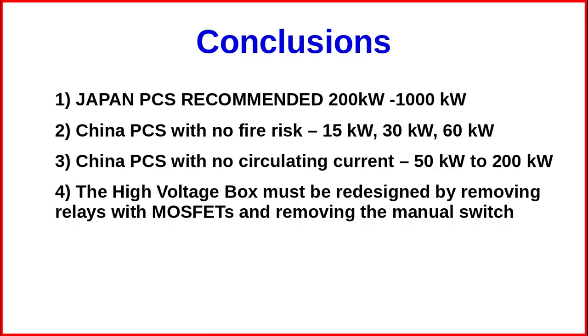Conclusions. One, Japan PCS is recommended for the range 200 kilowatt to 1000 kilowatt. Two, China PCS with no fire risk: these low voltage China PCS are recommended for BESS capacities of 15 kilowatt, 30 kilowatt and 60 kilowatt. Three, China PCS with no circulating current: use the high voltage China PCS for the capacity range 50 kilowatt to 200 kilowatt. Point number four, the high voltage box must be redesigned by replacing relays with MOSFETs and by removing the manual switch.